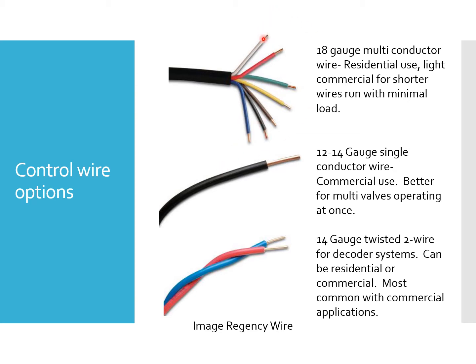So this white wire, if you had all 6 valves in one location, you would strip this wire back pretty far so that you can get this white wire out and daisy chain it and share the same common from one valve to the next, where all of the rest of the color wires will go to their own individual valves. This next valve wire is a 12 or 14 gauge single conductor wire, which is normally used for commercial use, and it's better for multiple valves operating at one time, so it would have a larger load being carried through it. Also, it can go for a longer distance.